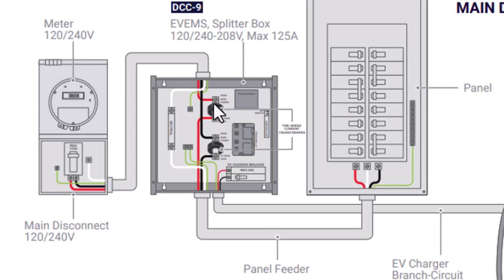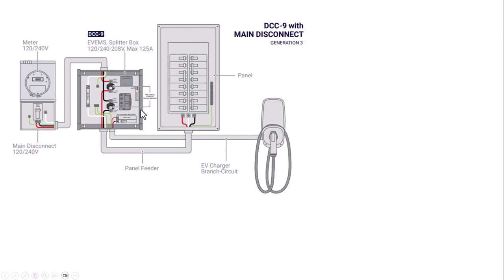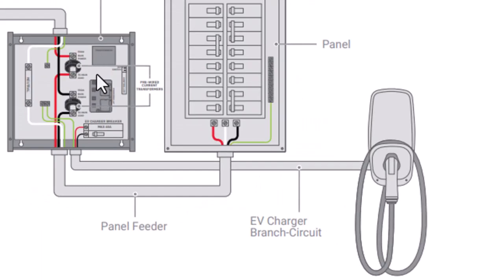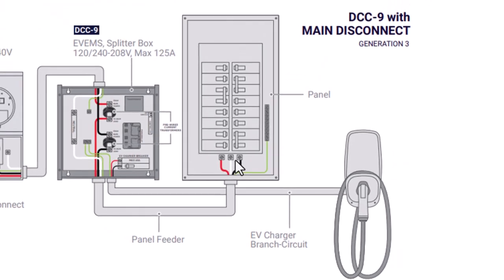And you can see it runs through this circular object, and this is the current transformer that basically senses the current that's going through the wire. The way it works is by monitoring the electromagnetic field that that current generates. So you have two of these that are monitoring the amps within each of the hot legs. And the signal from this current transformer is then basically controlling this relay right here that will switch the power from the EV back to the main. So this is the EV charger, and it goes right to this EV charger right here. And then the power internally will split into the relay, which then goes to your EV charger. And the main feeder goes right to your main panel right here.